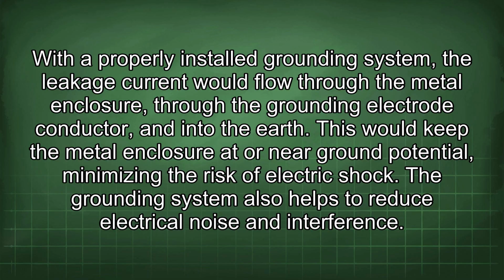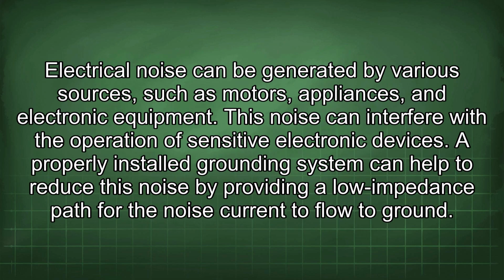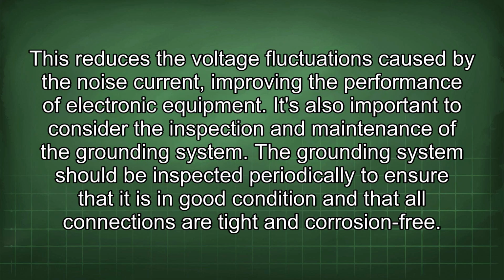The grounding system also helps to reduce electrical noise and interference. Electrical noise can be generated by various sources, such as motors, appliances, and electronic equipment. This noise can interfere with the operation of sensitive electronic devices. A properly installed grounding system can help to reduce this noise by providing a low impedance path for the noise current to flow to ground. This reduces the voltage fluctuations caused by the noise current, improving the performance of electronic equipment.